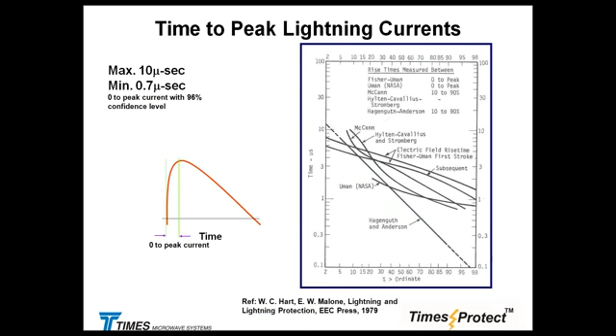Now, people are saying, well, I have a coaxial cable, I've got nice shielding, I install my grounding kit at the base of the antenna, then another one at the horizontal transition over the cable tray, and then I'm doing my grounding kit basically at the entrance at the bulkhead. Why do I need inline protectors? If you take a look and do a test, everybody knows what their system impedance at the frequency of the radio is going to be. But if you ask people, hey, what's your system impedance at 10 megahertz? I don't know. Or what is it going to be somewhere between 1 to 10 to 15 megahertz? Nobody really knows that.